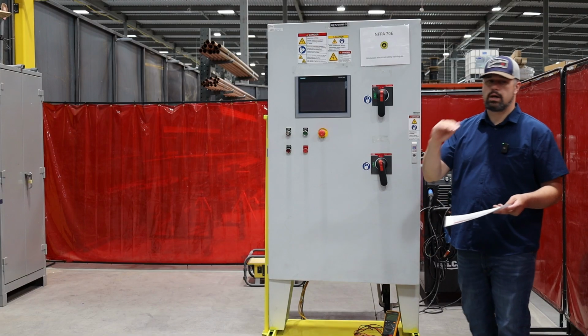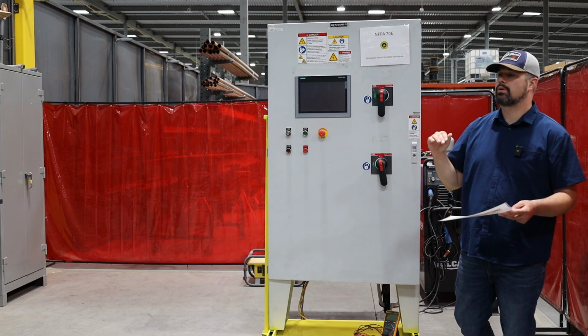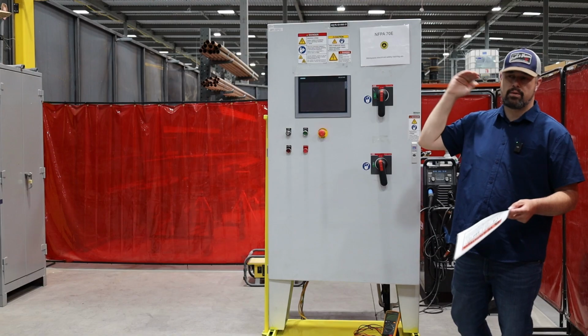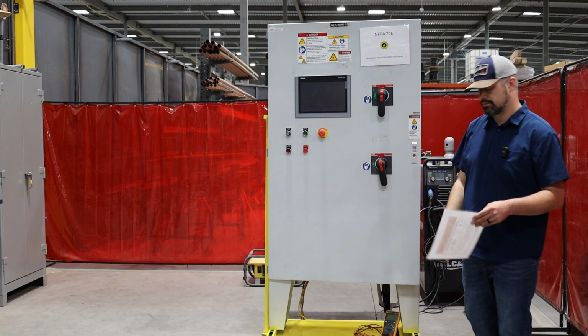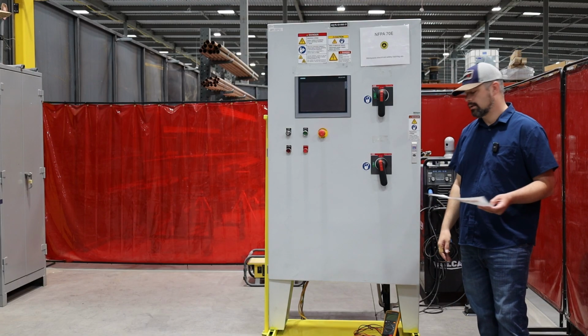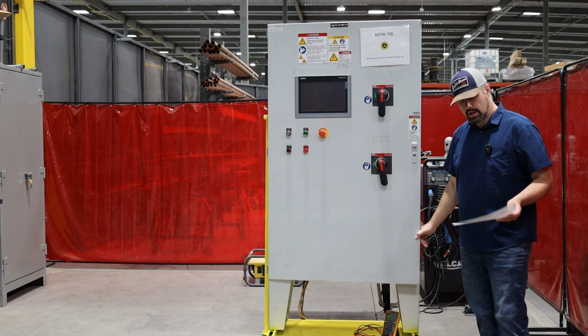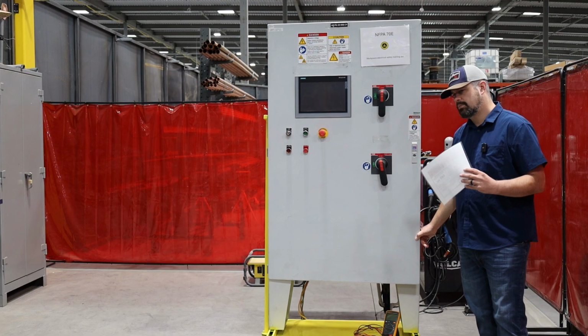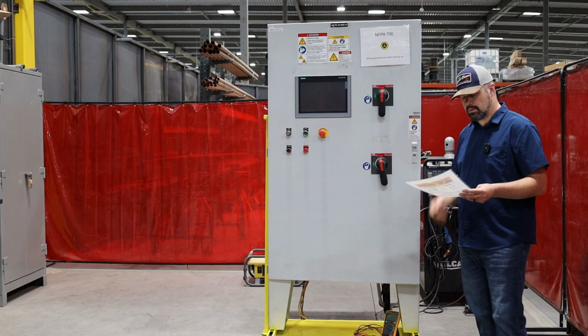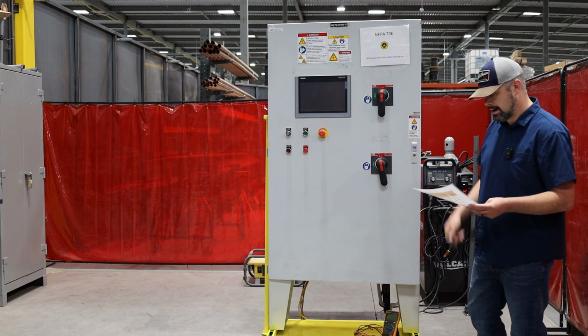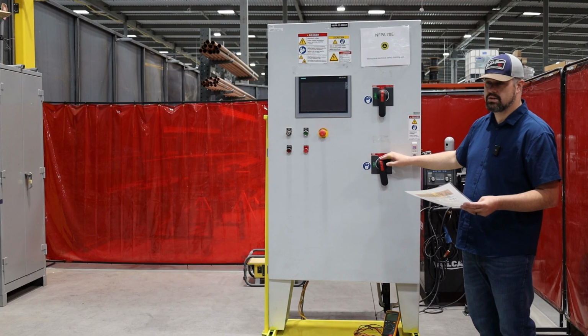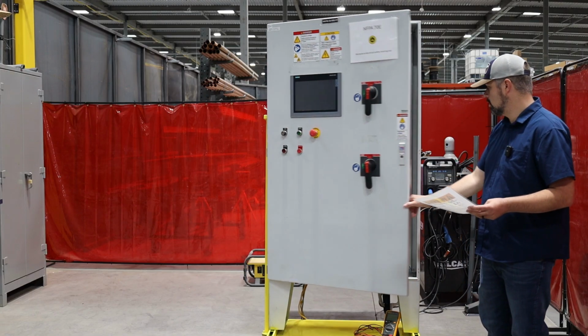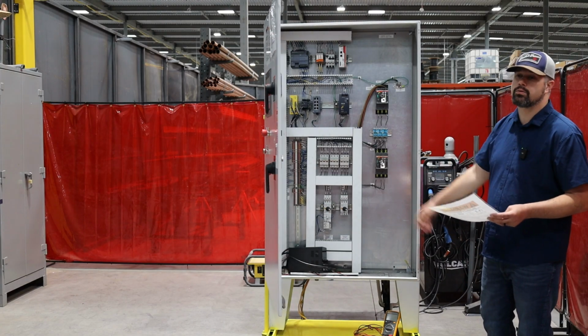Again, there are OSHA and NFPA requirements. Every employer has the right to go a step above and beyond that just to play extra safe, and that's absolutely what we're going to do here. So we've got our barrier set up at 42 inches. We've got the appropriate PPE that we need to be within the 18-inch boundary. And so we're just checking to see if there's a breaker trip. So we pass it up, we open it up. Well, look at that. There is a breaker trip, okay?